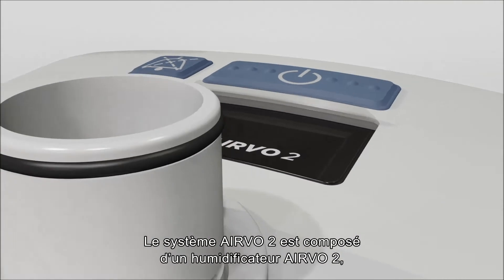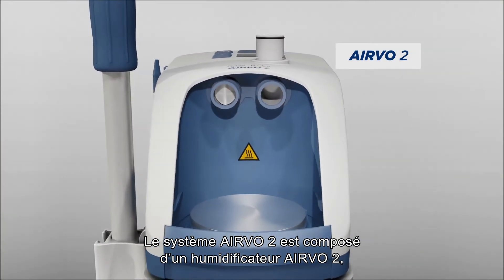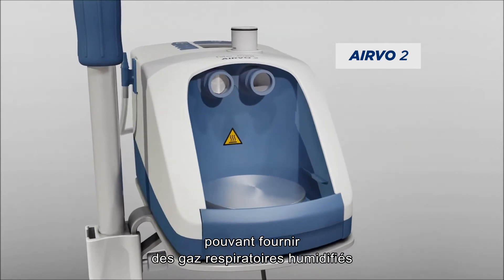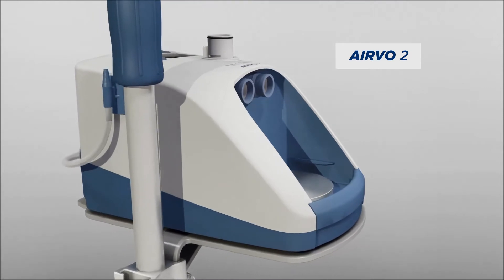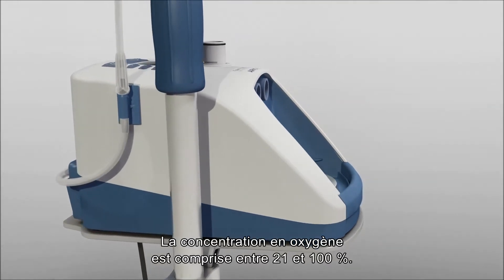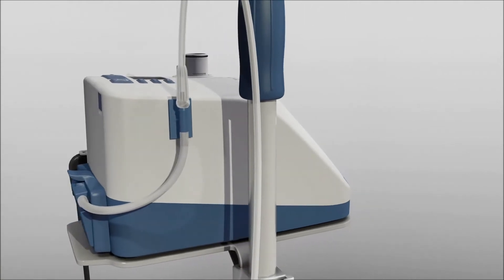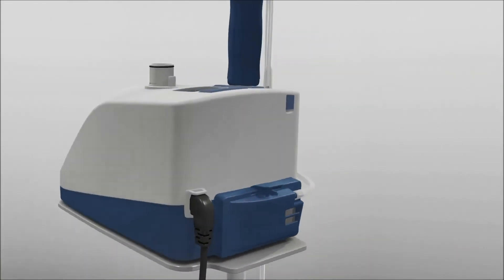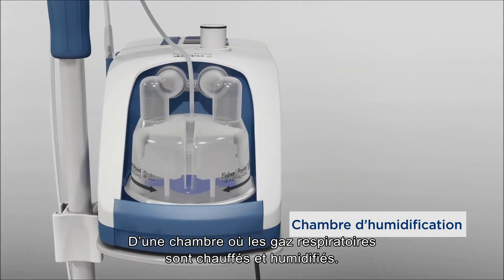The AIRVO 2 system consists of the AIRVO 2 humidifier, which can deliver humidified respiratory gases at flows from 2 to 60 litres per minute and oxygen concentrations from 21 to 100%. A water chamber, where the respiratory gases are warmed and humidified.